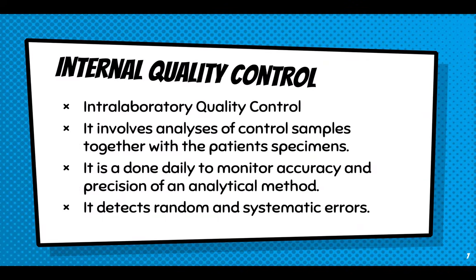Okay, so let's dig into our discussion for this morning. Internal quality control is also known as your intralaboratory quality control. Again, what we're trying to do is to compare your QC result from day 1 to day 2, from day 3 to day 4. So technically, what you're trying to compare is the quality of your results each and every day. It involves analysis of control samples together with the patient's specimen. But I want to emphasize that you do your QC first before you run your patients.